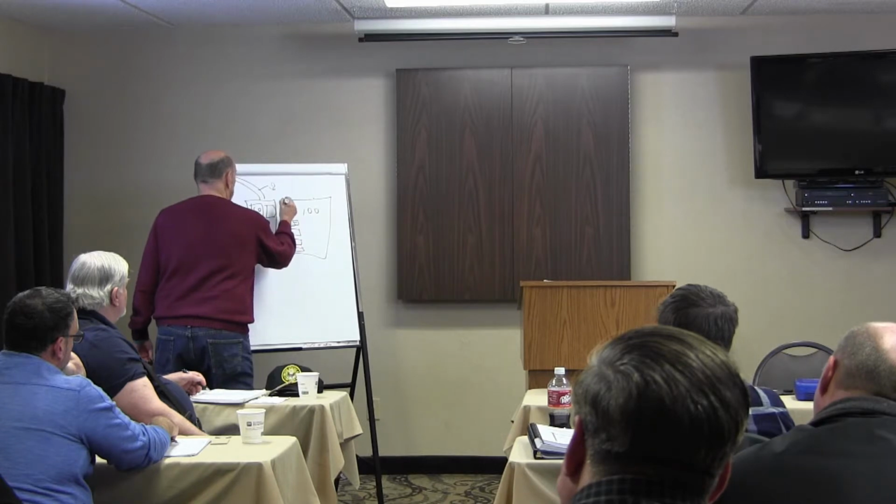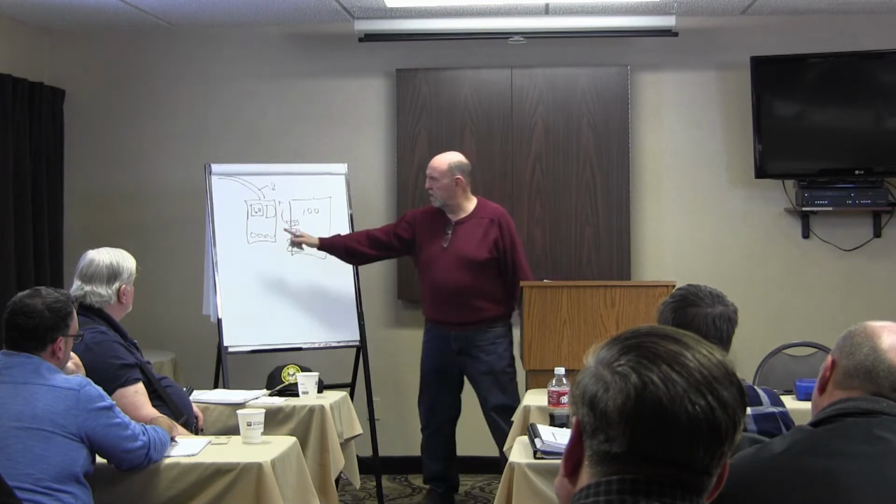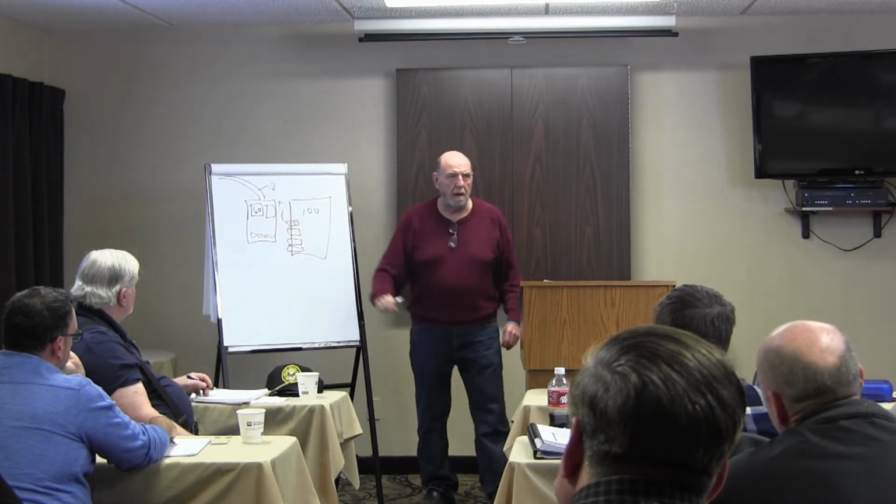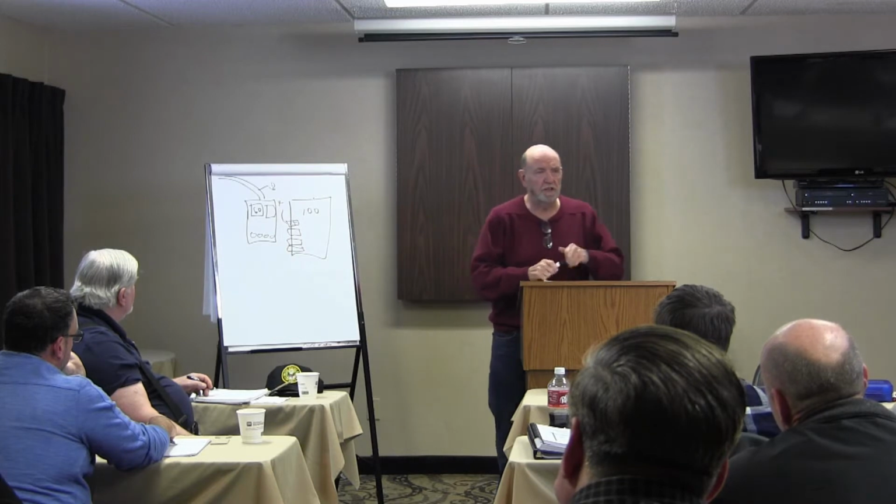Because here's 15 amps. Well, it only takes 4 coffee pots to pop that. Now, that breaker may not pop right away. It also takes a while for that wire to heat up and for the insulation to catch on fire. So a lot of people live with these problems all the time because it's only 3 or 4 or 5 minutes of overheating. That's where you'll see the singe marks when you open up a panel, that it was too hot for a short period of time. Not hot enough for anything to catch on fire, but hot enough to leave its singe marks behind.